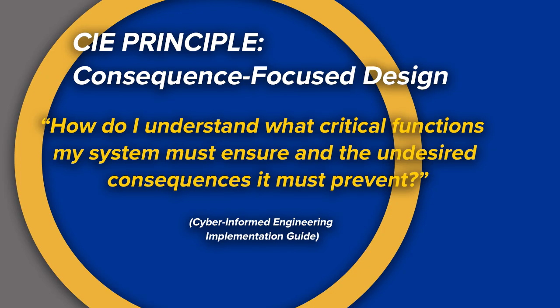For our use case, the main CIE principle we are looking at is consequence-focused design. That is what our lab is about. We are showing that if a circuit breaker is opened, like with the Ukraine use case we're looking at, where attackers got access to the system and were able to manipulate the circuit breakers to open them, if that happened with the generator, it can not only disconnect people from power, but it can also cause damage and instability to the generator itself.